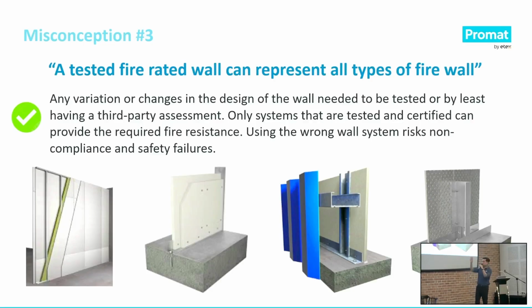Even when we zoom into just the one with mineral wool—if your contractor changes the distance of the framing, say from 610 millimeters to 1.2 meters, it gives different results. So as a system owner, we have to get it fire tested to prove the fire rating. A wall system itself cannot represent everything. If somebody proposes a fire-rated wall, 2 hours, please look at the system itself, what it comprises, and whether it actually suits what you want on your project site.